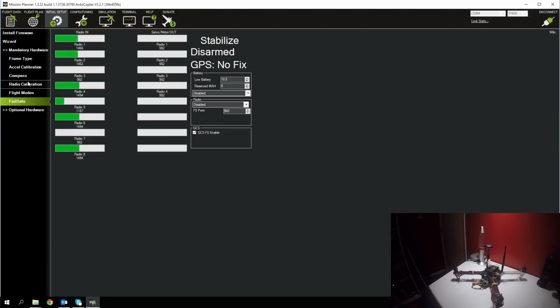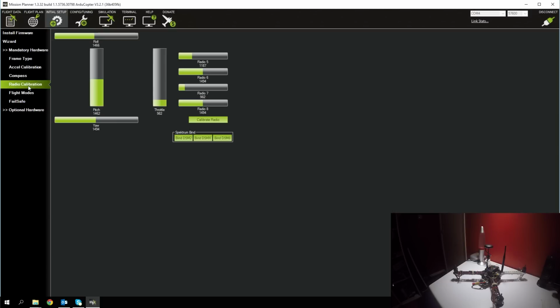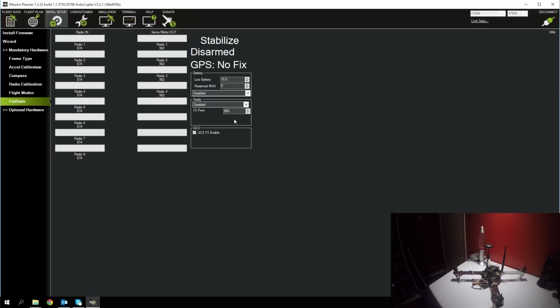Then if we go back to the radio calibration screen, if I turn the transmitter off, this value should drop low here. So let's do that. There we go - you can see it drops to 874, which is well below what I've set on the failsafe. So that should failsafe, and we can actually test that.